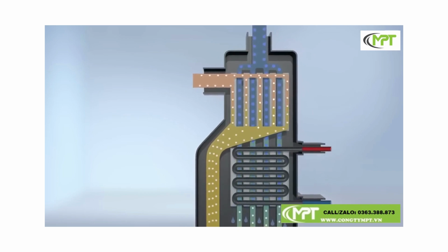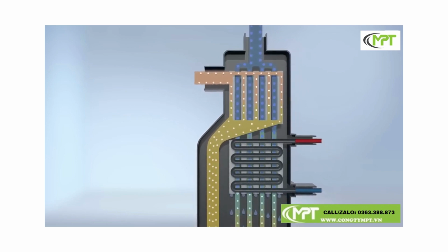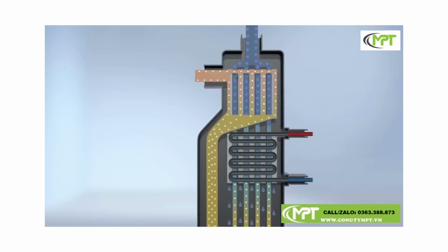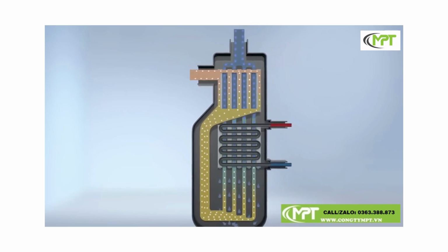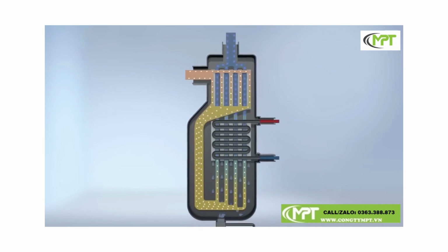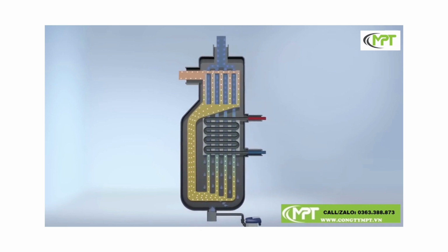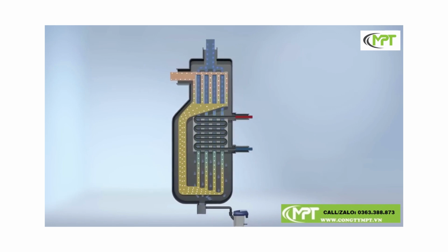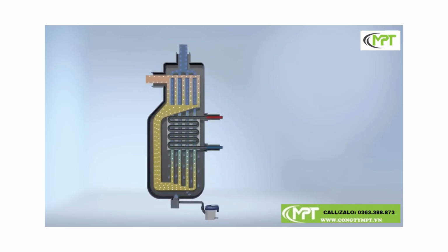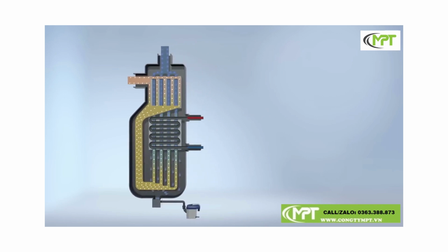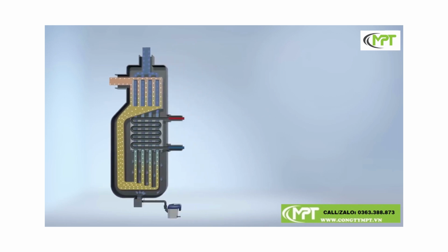The countercurrent principle used within the air-to-air heat exchanger already increases the drying effect and the energy efficiency of the dry point RA Eco. Thanks to the streamlined construction, the compressed air passes almost resistance-free through the vertical heat exchanger without noticeable deflection. This minimizes pressure loss, thus lowering the system's energy consumption.